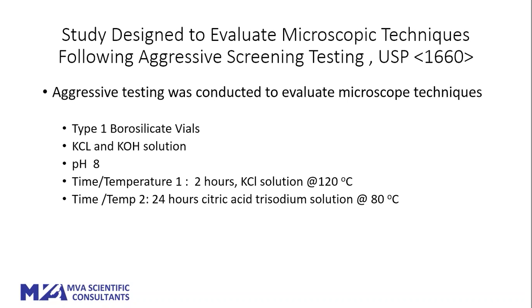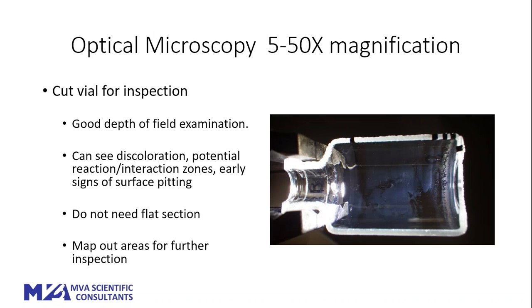We designed a study to evaluate containers using these different techniques, following the USP 1660 method. We set up a design with a pH of 8 using potassium chloride and citrate solution. The first step was to fill the containers with KCl solution at pH 8 and allow that to sit at 120°C for two hours. Following that, we decanted the solution and added the citric acid solution, which sat at 80°C for 24 hours. After that period, we prepared the samples for analysis.